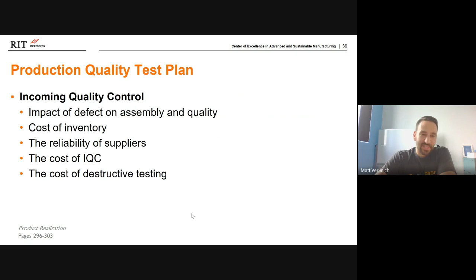So, production quality test plan. This is also going to look different for fabricated components. Things that are coming from an outsourced fabricator, like a PCBA house or an electronics contract manufacturer, will likely have their own system set up to do those tests. However, you want to make sure that those tests are actually defined according to the parameters that you need them to be. If they just go with some industry standard without understanding exactly what the functionality of your product is, you'll then be left with a bunch of parts that might not work, and the manufacturer will be able to say, it doesn't matter, that wasn't the scope of our agreement.